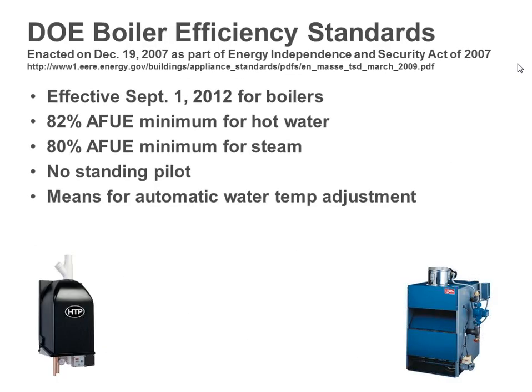Boilers' minimum efficiency is also changing, much sooner, in September of this year, 2012. It's not going up very much though. The minimum efficiency boiler for a hot water system today is 80%; the new minimum will be 82%. Unlike furnaces, they're not mandating a condensing appliance, so you don't have to change the venting. Meeting this new boiler standard in a home will be fairly easy, whereas meeting the new furnace standard will be a lot of work because of the venting difference.